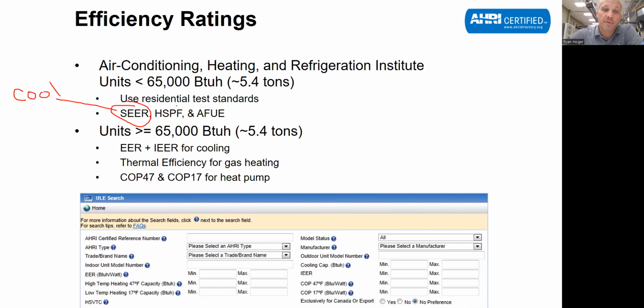If I happen to have a heat pump, it would have a SEER rating for cooling and it would have an HSPF, heating seasonal performance factor, for the heat mode. Same piece of equipment, run through two different tests, one with the reversing valve set for cooling, one with the reversing valve set for heating. I should point out that now we don't use SEER and HSPF. Now we use SEER 2 and HSPF 2.